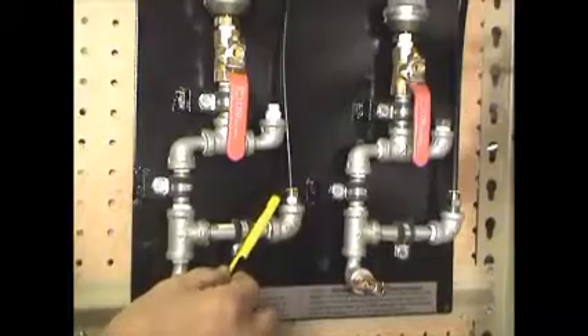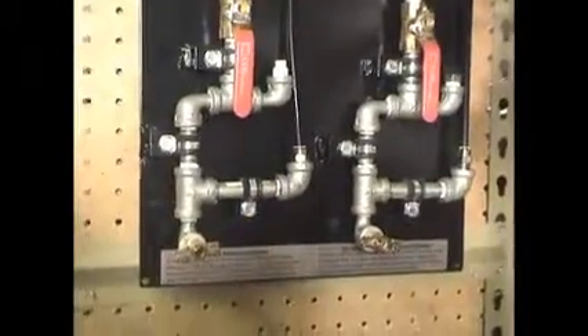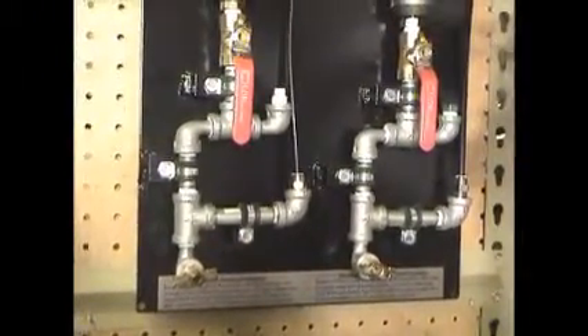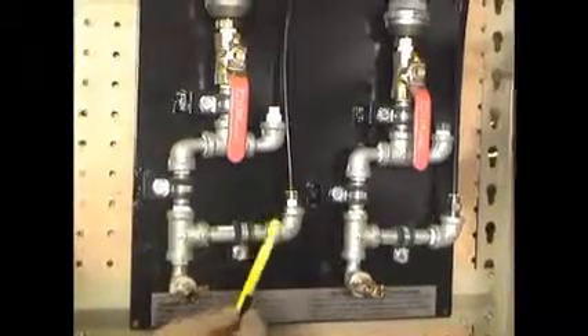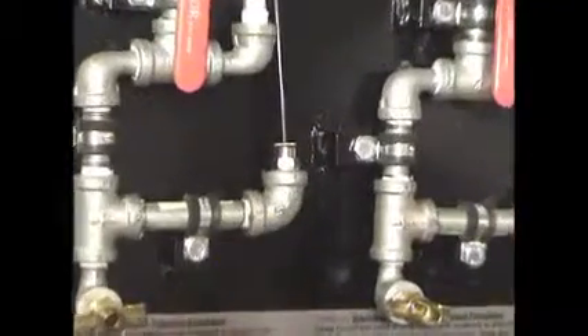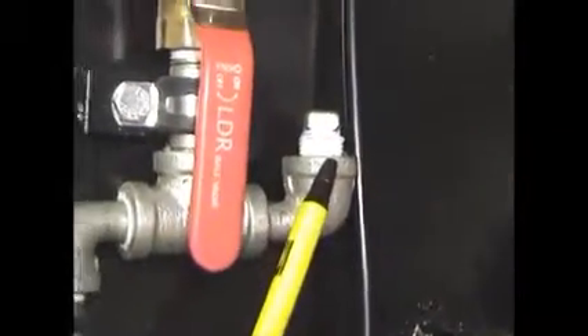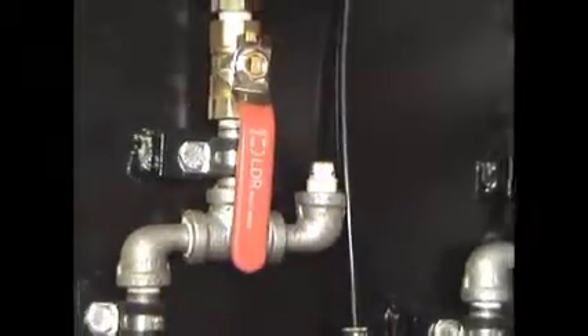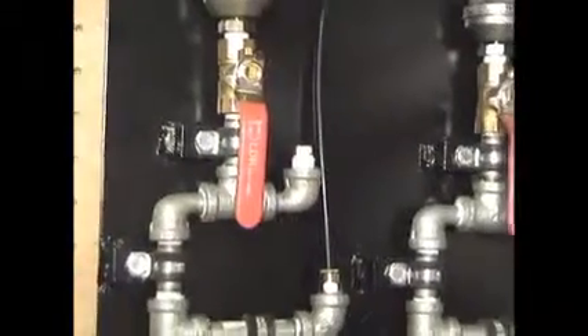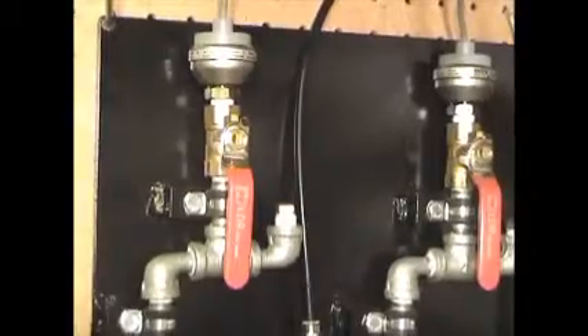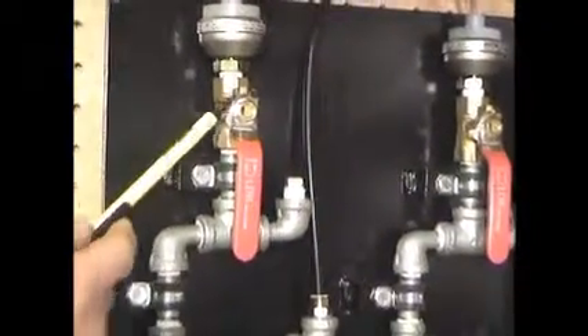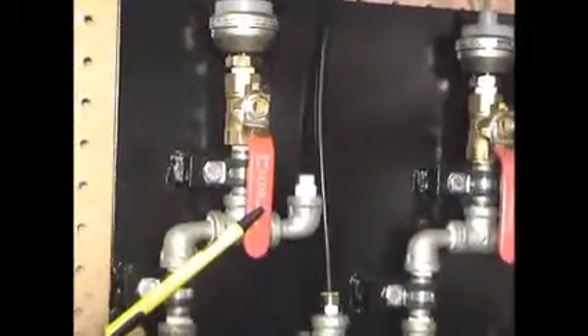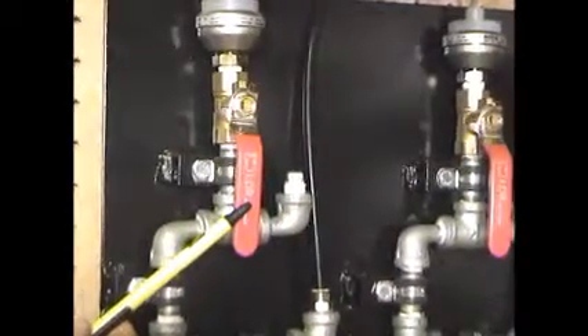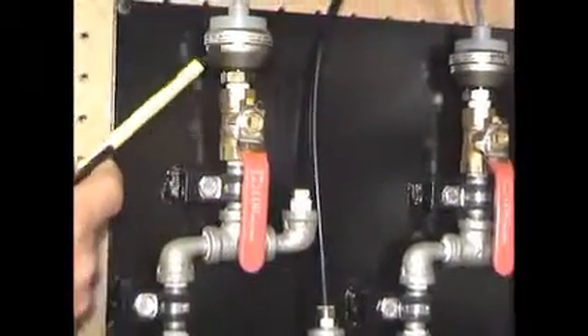A vacuum hose coming from a standpipe mounted on the suction pipe ahead of the pump is attached to the bottom elbow. The top elbow has a plug in it and can be removed and replaced with a line going to a manual gauge, vacuum gauge if desired. During operation, make sure the ball valve handle is positioned down or in its open position, so vacuum can be introduced into the vacuum transducer.